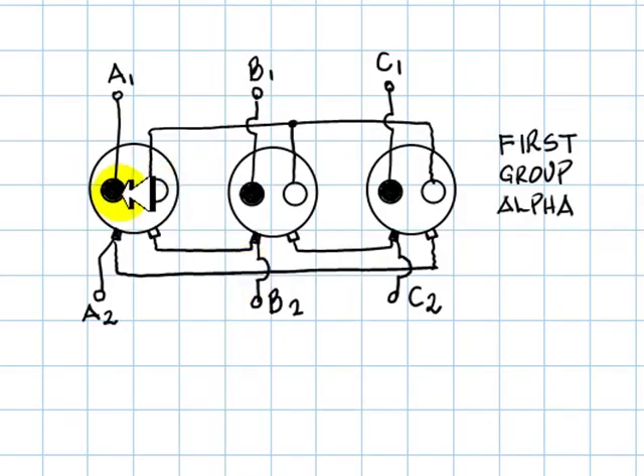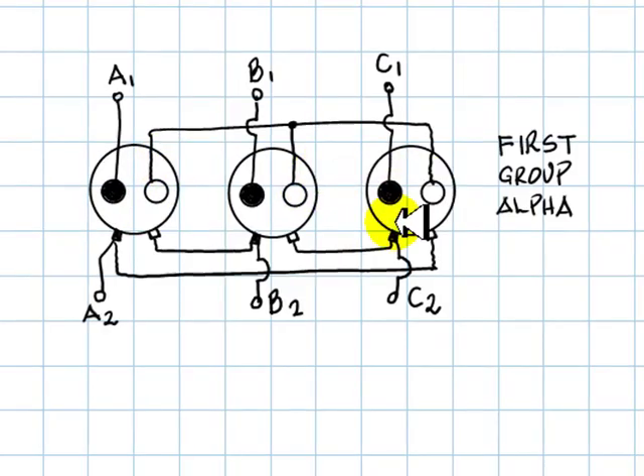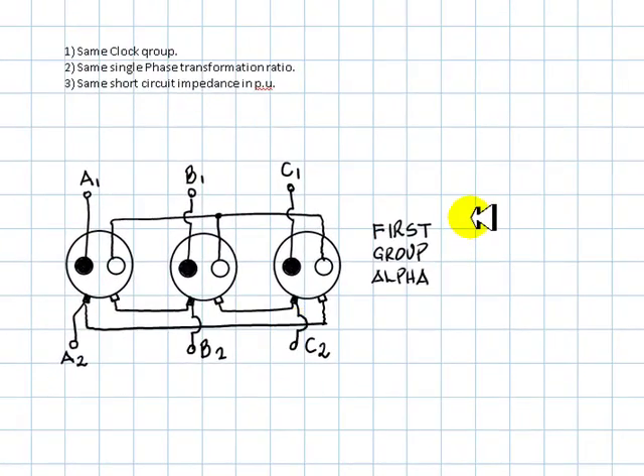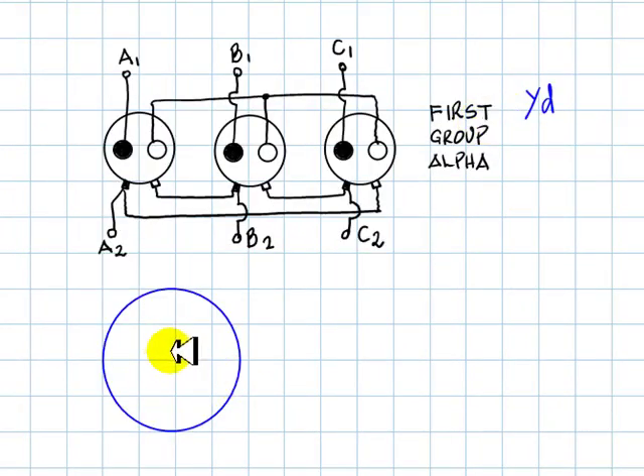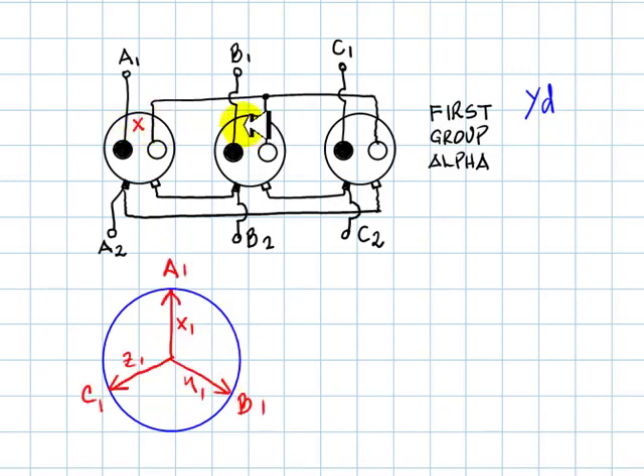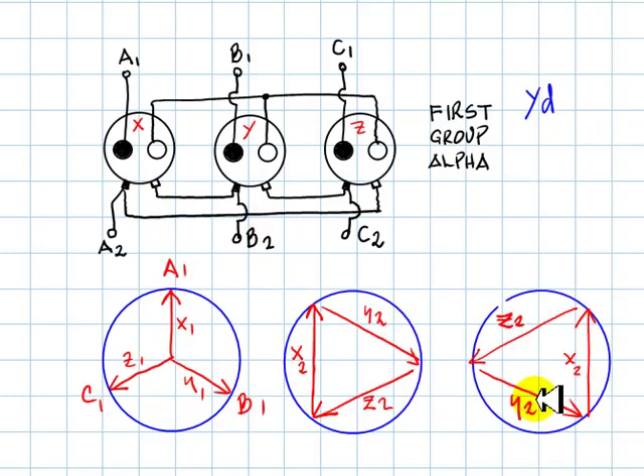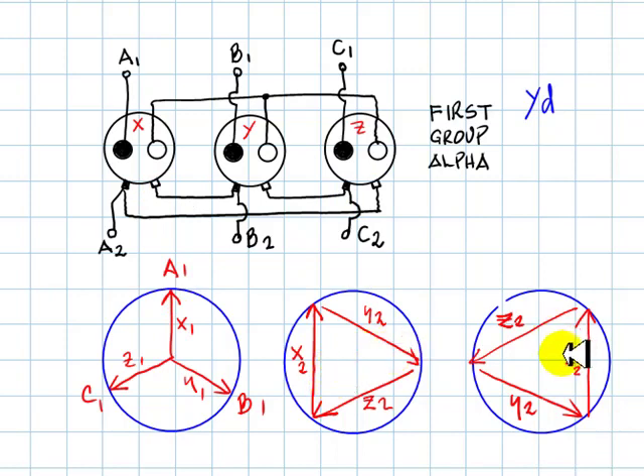Group Alpha has primaries connected in a Y and secondaries connected in a delta — a Y-delta connection. For the primary in a Y, the standard connection allows us to label the transformers as X, Y, and Z. The secondary voltages are in phase with those, but connected in a delta. Only two possibilities exist for the delta of the secondary, given the phases imposed on those three coils by the primary voltages.